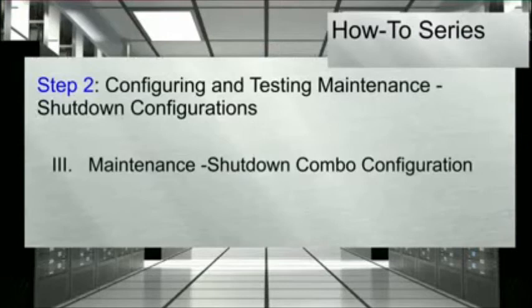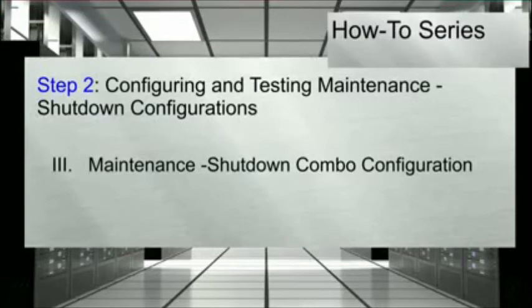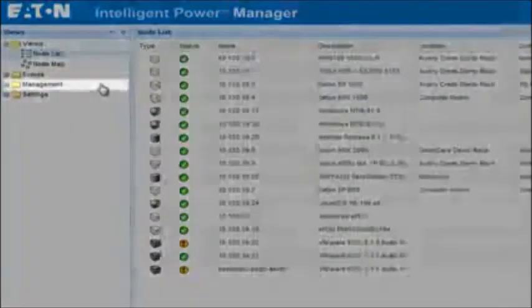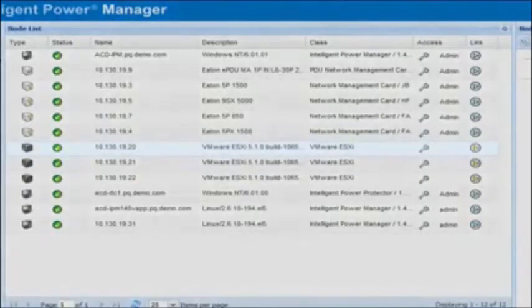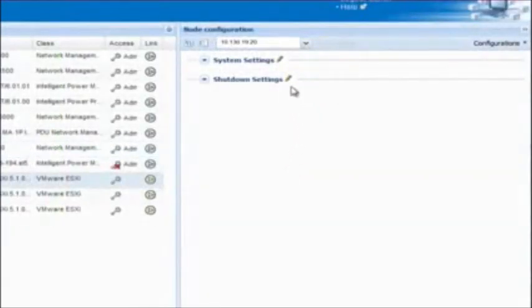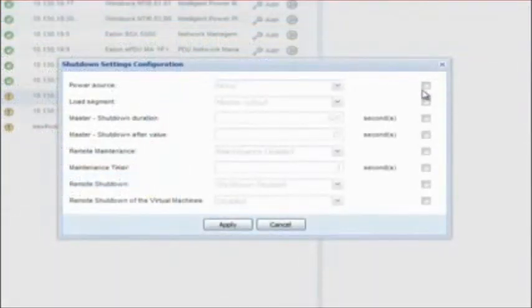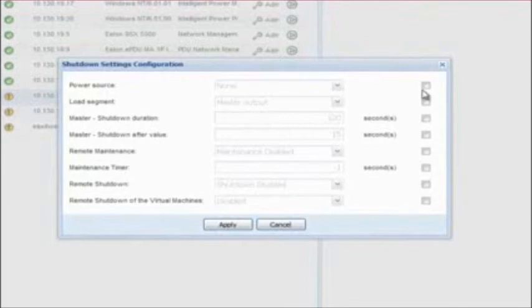The last mode of escalation we will review will be the maintenance shutdown combo configuration. Once the UPS supporting the selected ESXi host experiences a power event, IPM will trigger the maintenance mode. Once all of the VMs have been migrated into other available hosts, the shutdown mode will be initiated. In order to set the parameters, start from the IPM view screen. Select the folder titled Management and click on the option for Node Settings. Choose the VMware ESXi host that you would like to configure. Once selected, the Node Configuration pane will open to the far right of the screen. Click on the pencil icon beside the option titled Shutdown Settings. The maintenance shutdown combo configuration will need the following parameters set.